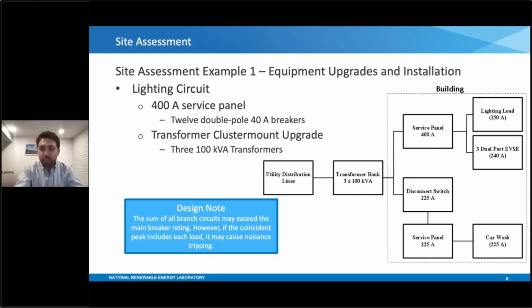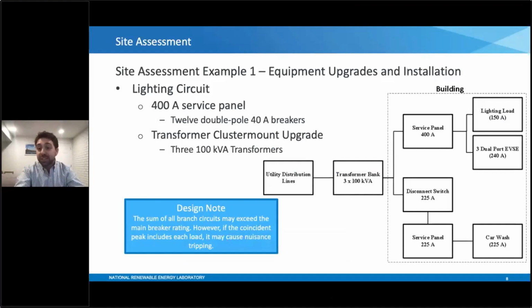About 240 amp rating is probably a good bet here, and that'll serve the 192 amps that the 6 EVSE will require, and that's just a basic 6 times 32 there to get the total amperage rating. Something else to consider, because we're upgrading this circuit, we'll need to look at the main breaker rating. And as I mentioned before, the sum of all branch circuits may exceed the main breaker rating. However, if the coincident peak includes each load, it may cause nuisance tripping.